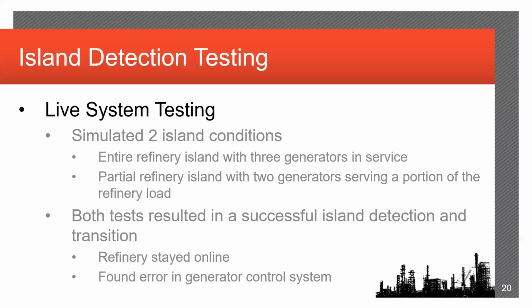So the good people at the refinery actually allowed us to do live system testing on this, and this is really the big test. We can prove in the lab that our logic works. We can prove in the field that all of the IEDs are sending the correct information from point A to point B. But actually simulating an island condition, and when I say simulating, this was done on an in-service live system. So the generators were online. The refinery electrical system was connected to the utility, and they allowed us to do two live fire tests. The first one was an entire refinery island with 3 generators in service.